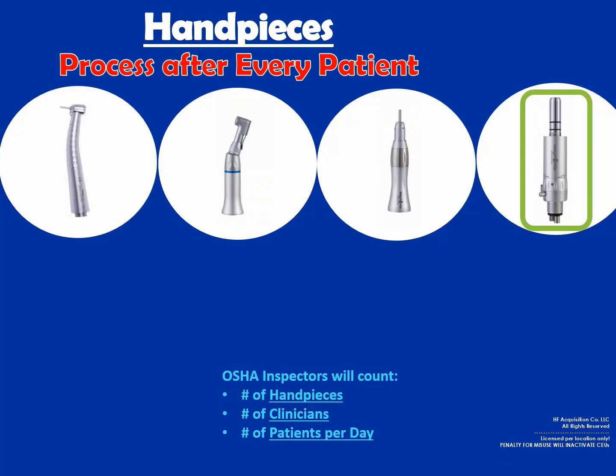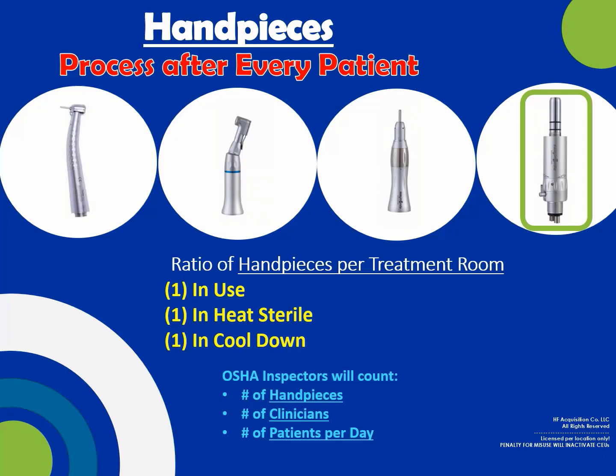Additionally, all handpiece components need to be heat sterilized after every use. This applies to high-speed turbine handpieces, autoclavable prophy angles, contra angles, and most importantly, low-speed motors. OSHA inspectors follow this formula to ensure you are implementing surgical grade levels of handpiece sterilization. They will count the number of handpieces, the number of clinicians, and the number of patients seen per day at your office. The ratio of handpieces per treatment room should be 3. This accounts for having 1 handpiece in use, 1 in the heat sterilizer, and 1 in a cool-down process.